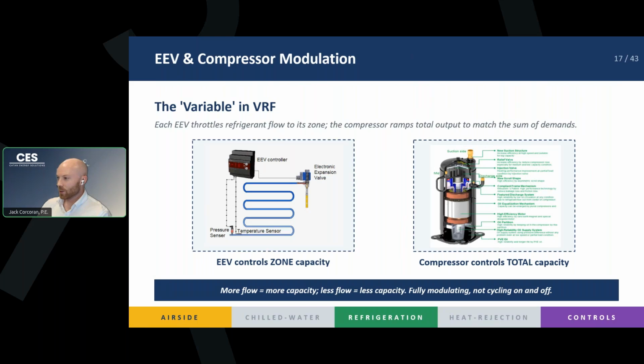Conversely, when your zone's satisfied and the temperature in your room is exactly where you need it to be, that electronic expansion valve, or your EEV, starts to close. Less refrigerant goes through the coil. You have less evaporation or condensing, and you have less heat transfer, right? So all it is doing is modulating the flow at every indoor unit so that every indoor unit can operate off its own temperature demand, right? So you're not affecting your whole system when one zone is satisfied. You're actually catering to each individual zone's demand.